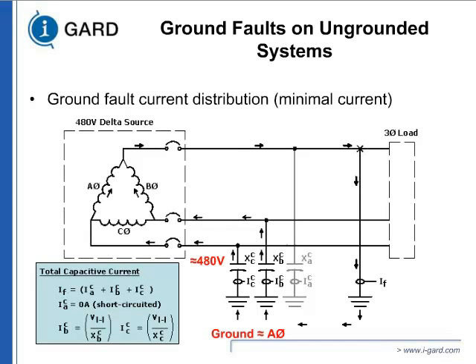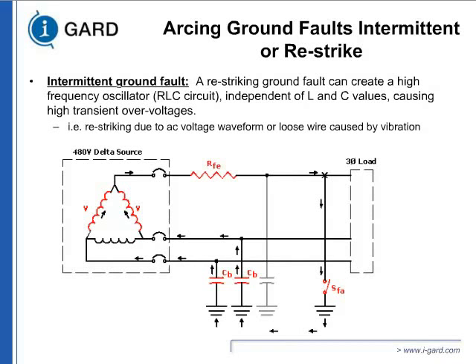Now, intermittent faults are the most dangerous. One, they are not easily detectable. Second, they keep raising the voltage. On your sketch, you see a switch, which is just for modeling. When the switch is open and closed, the ground fault flows. You can imagine the switch is a very high fault system. It is closing and opening very fast, and that's where the arcing starts.